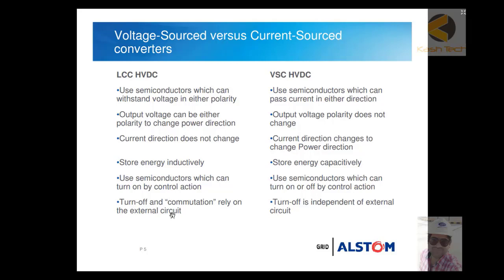In LCC, to change the current direction you must change the polarity of the voltage itself — it is not possible to change the current direction independently. Another difference: LCCs store energy inductively using reactors connected to the line, whereas VSCs store energy capacitively using capacitors. LCCs use semiconductors that can only be turned on by control action, whereas VSC HVDCs use semiconductors that can be both turned on and off by control action. In LCC, turn-off and commutation rely on the external circuit, whereas VSC turn-off is independent of the external circuit.